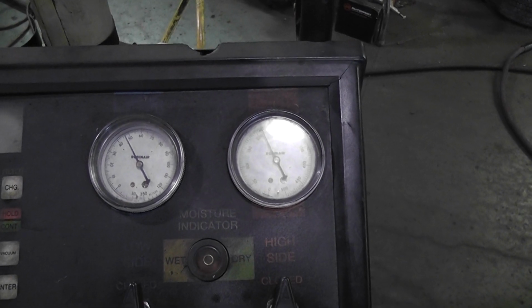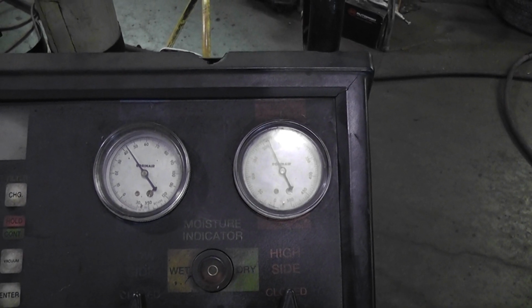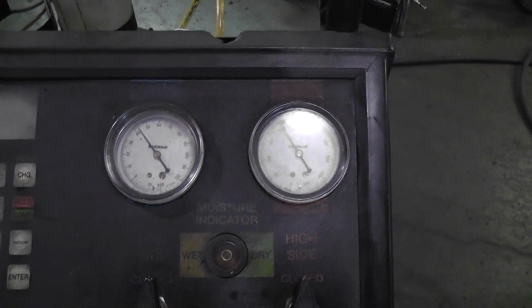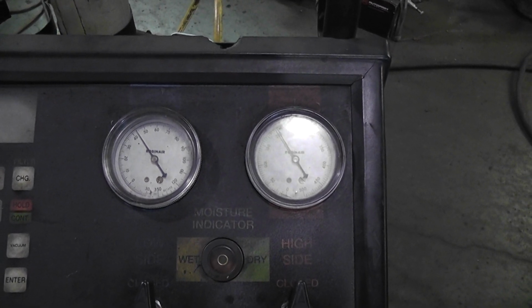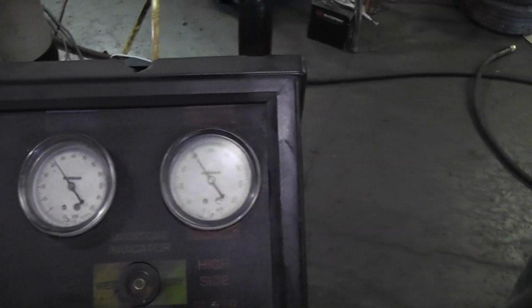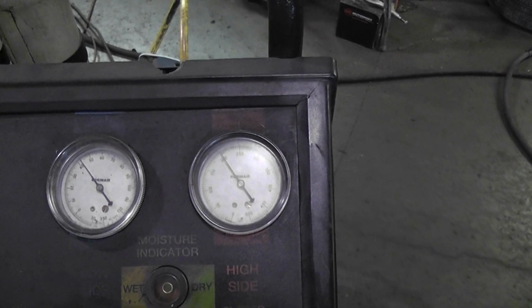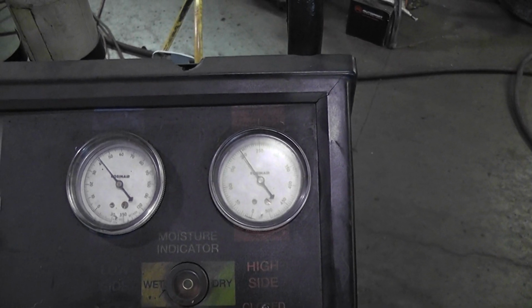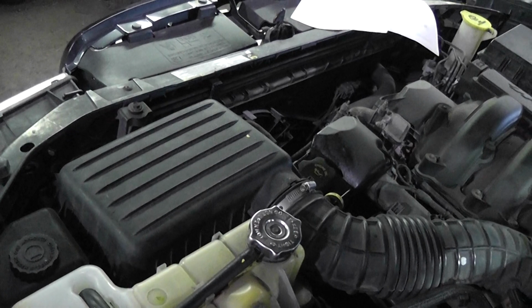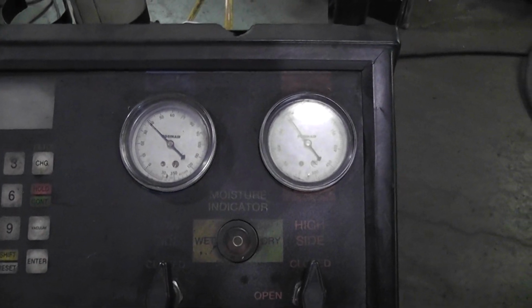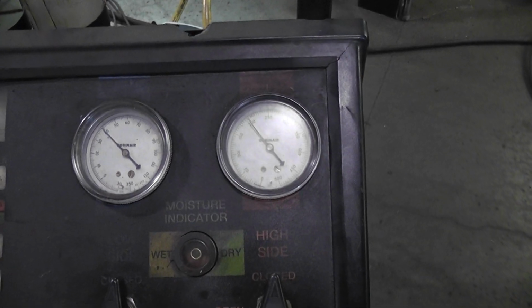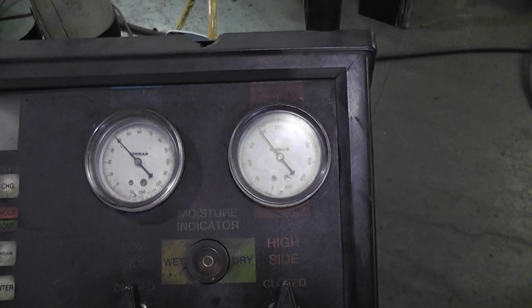Man, the pressures look terrible — yeah, it's equalizing out. Pulling it down to 40, hanging at 200, probably about 85 degrees out. I have the hood open so I might be getting less airflow. The high side is 200, that's not bad, and 40 actually isn't bad either.